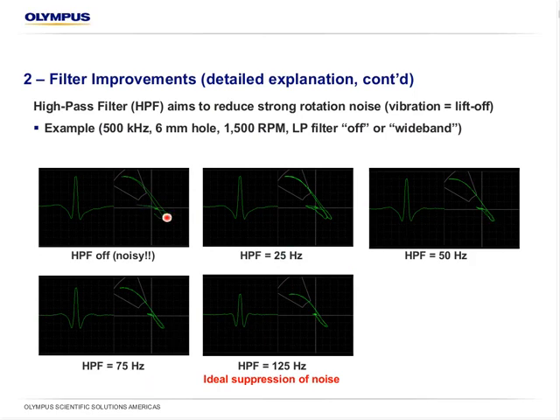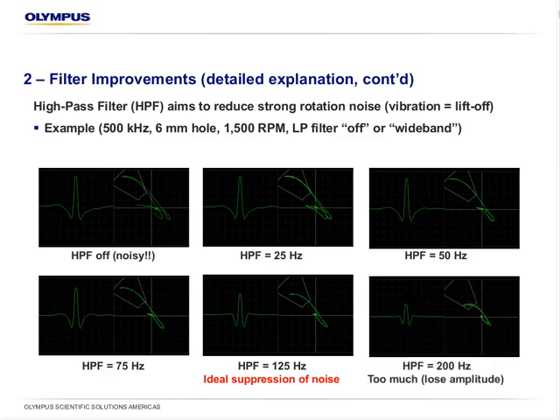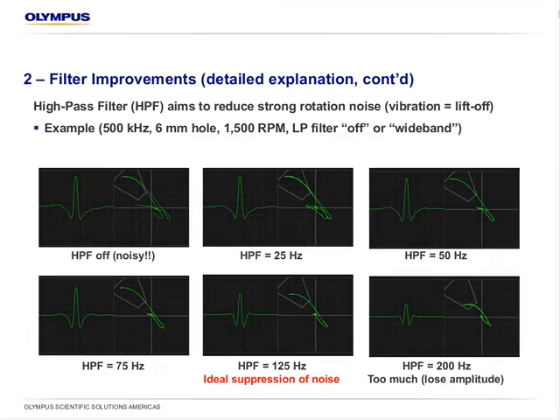So we can see that the background signal becomes smaller as we increase the high pass filter, up to a point where it gets ideal and there's almost no vibration left. There's quite enough of the track signal. If we keep increasing the high pass, we basically don't gain anything because it starts to decrease the amplitude of the track signal, and we don't gain much in signal to noise ratio after a while. So for that reason, we will say that the high pass of 125 hertz in that specific condition is actually ideal. All right, let's go to the low pass now.